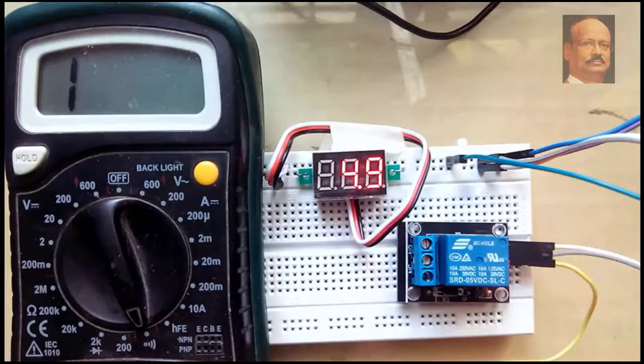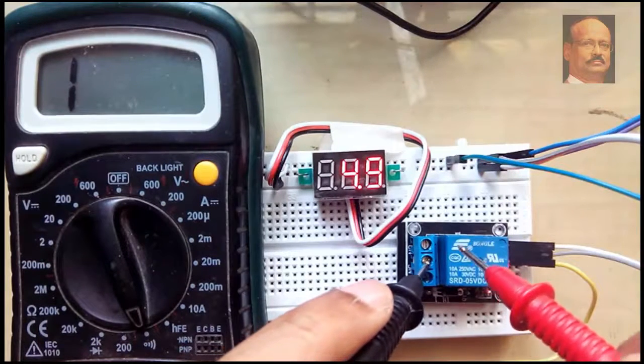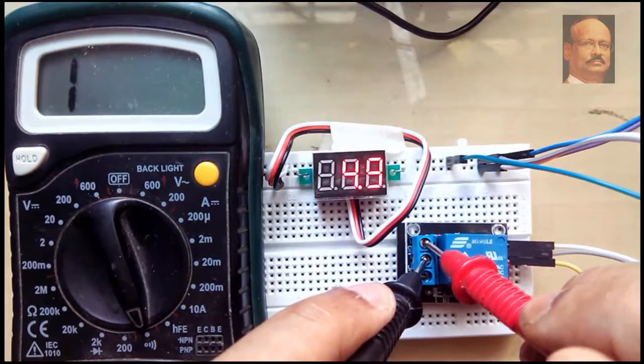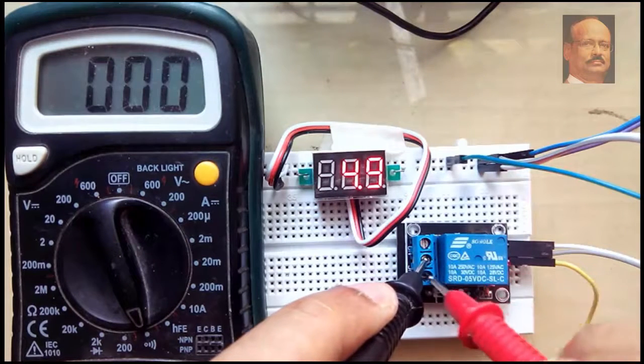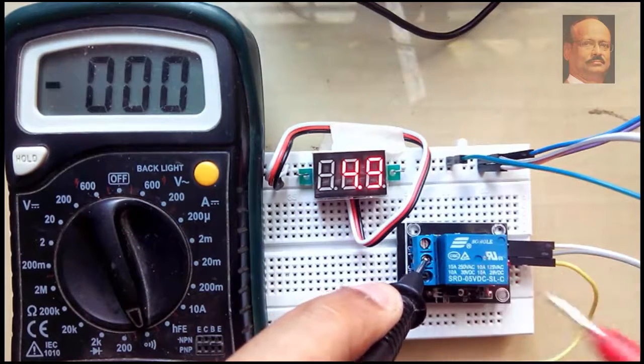And we will notice now that the common point to the NO point is now showing conduction, not this point. So this is the NO point.